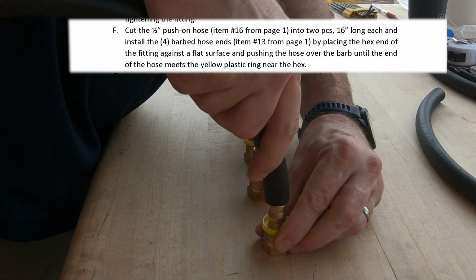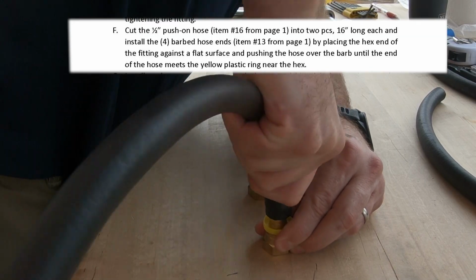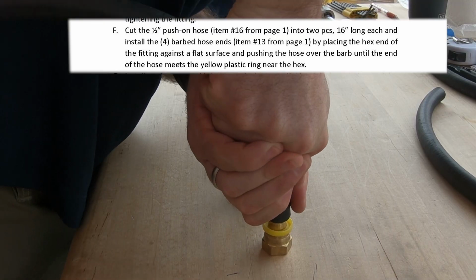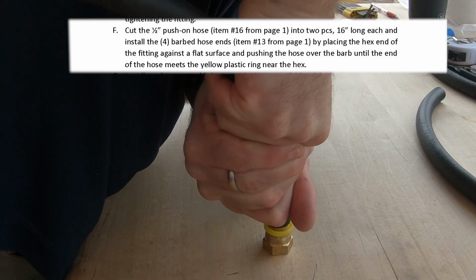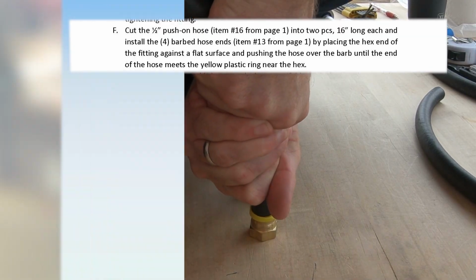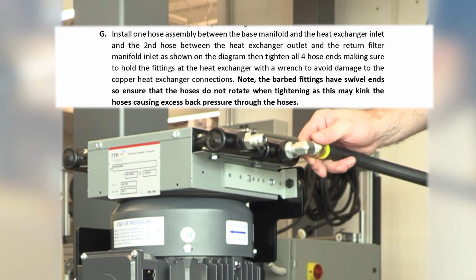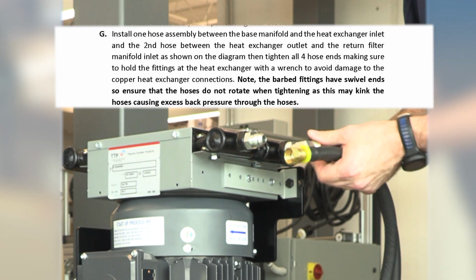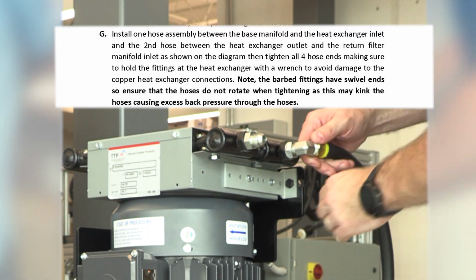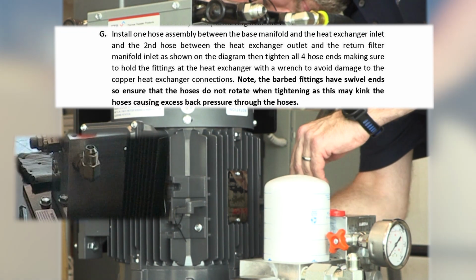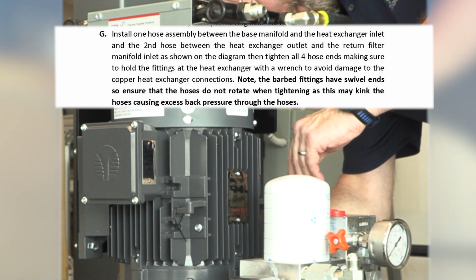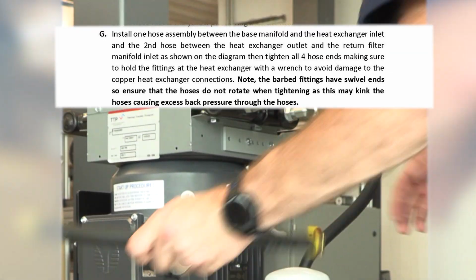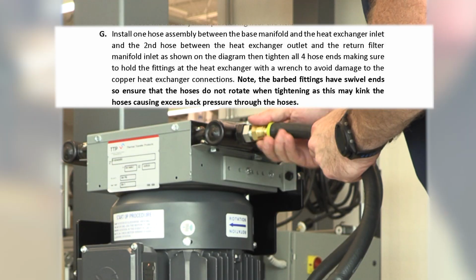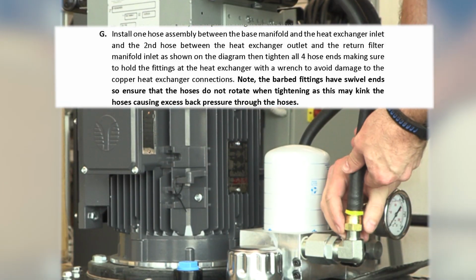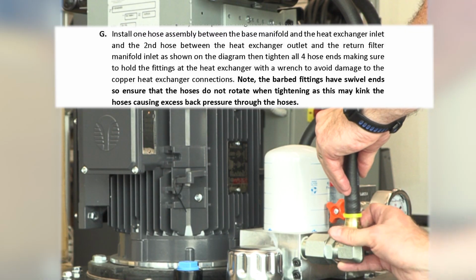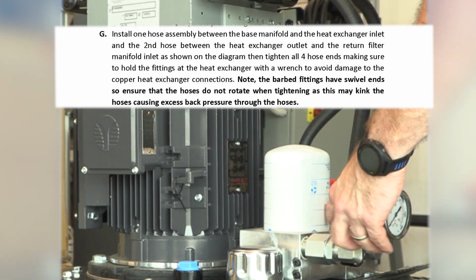This 1/2-inch hose needs to be cut into 2 16-inch pieces and installed by placing the hex end of the fitting against a flat surface and pushing the hose over the barb until the end of the hose meets this yellow plastic ring near the hex. Install 1 hose assembly between the base manifold and the heat exchanger inlet. And the second hose between the heat exchanger outlet and the return filter manifold inlet as shown. Then tighten all 4 hose ends, making sure to hold the fittings at the heat exchanger with a wrench to avoid damage to the copper heat exchanger connections.